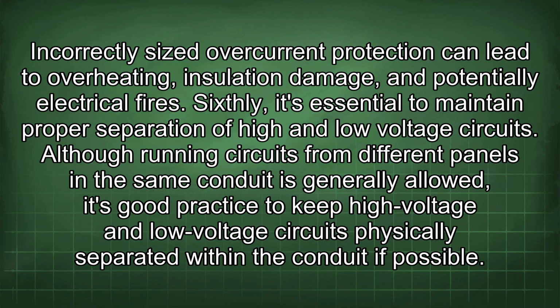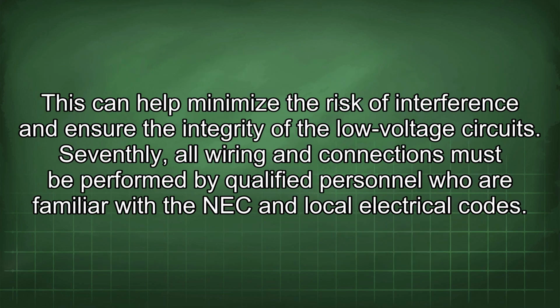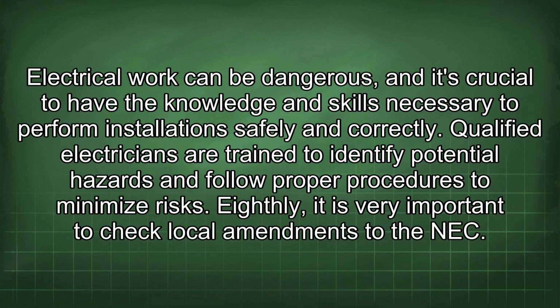Sixthly, it's essential to maintain proper separation of high and low voltage circuits. Although running circuits from different panels in the same conduit is generally allowed, it's good practice to keep high voltage and low voltage circuits physically separated within the conduit if possible. This can help minimize the risk of interference and ensure the integrity of the low voltage circuits. Seventhly, all wiring and connections must be performed by qualified personnel who are familiar with the NEC and local electrical codes. Electrical work can be dangerous, and it's crucial to have the knowledge and skills necessary to perform installations safely and correctly. Qualified electricians are trained to identify potential hazards and follow proper procedures to minimize risks.